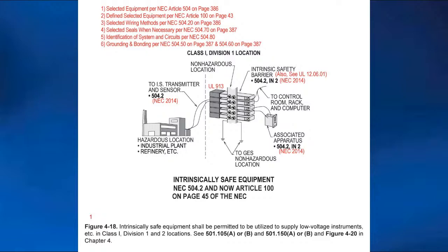And then let's see here. Oh, yeah. Now, sometimes the item number 4 in your illustration in the red is selecting your seals when necessary. And mainly in 504.70 on page 387 of the code, we would select those seals usually in 501.17 that deals with process equipment, where you'd have a pressure and a gas or vapor might pass through the core of the cable and create a hazard in a non-hazardous type area in some cases. So that's where you'd want to see if you need seals or not. Otherwise, you don't at 504.70.